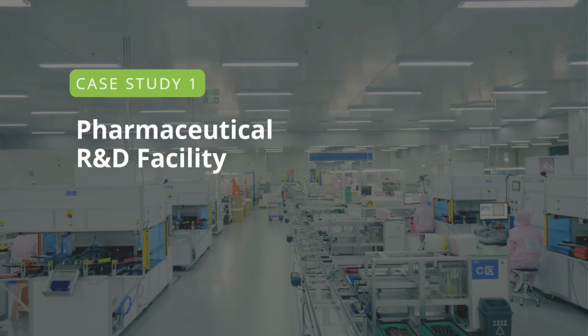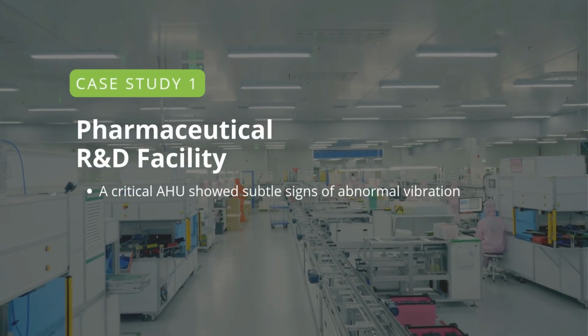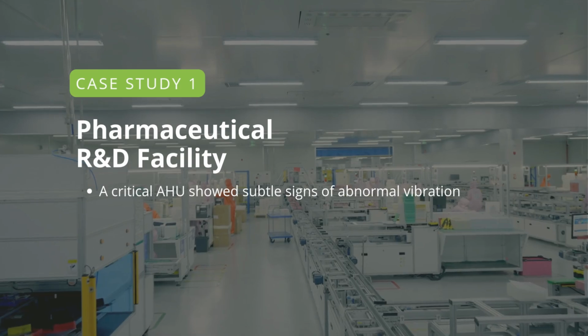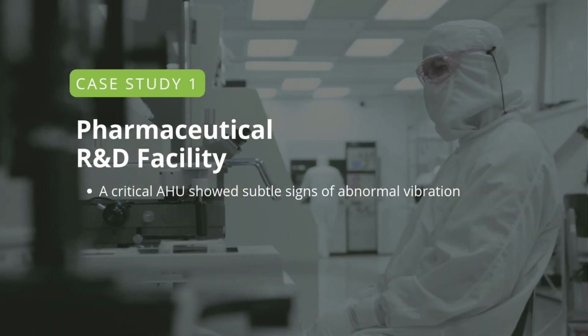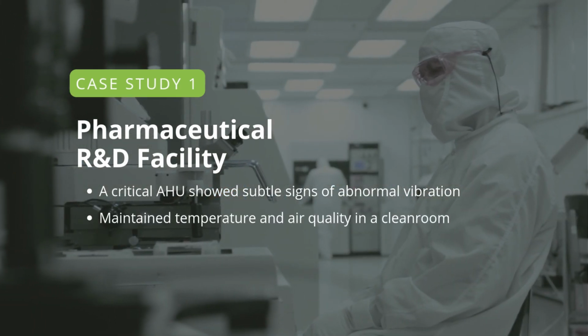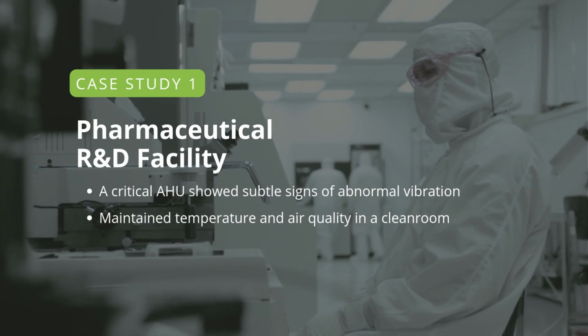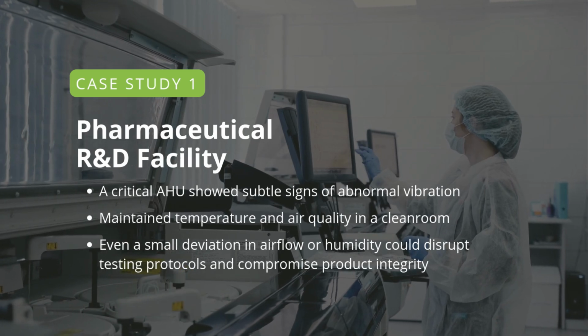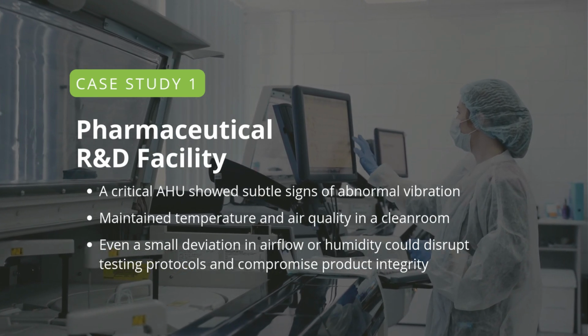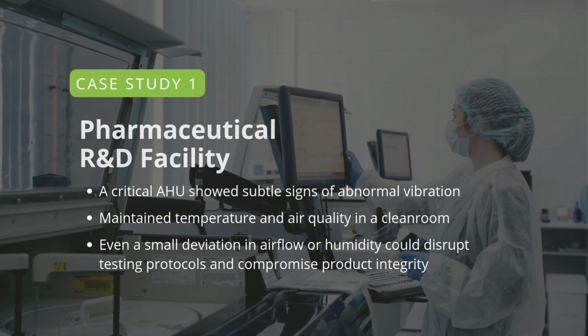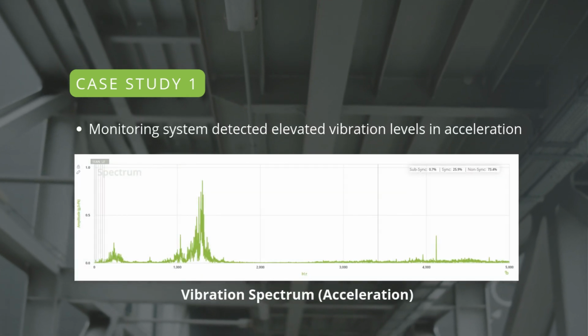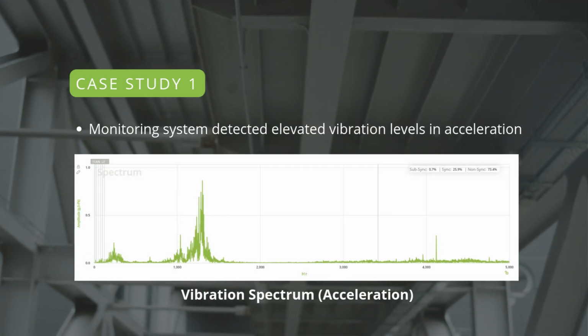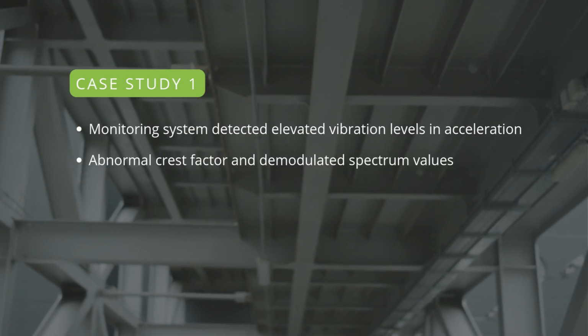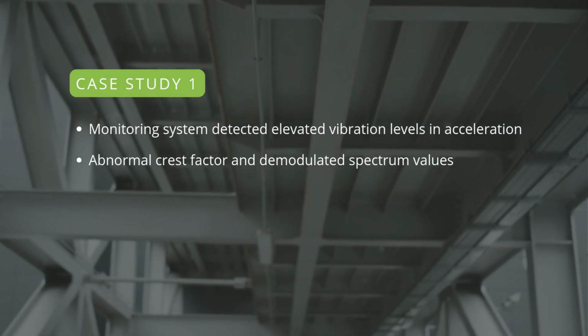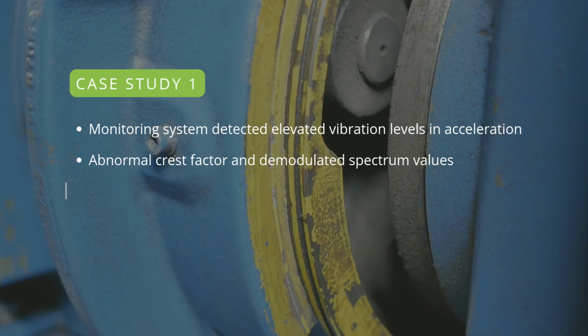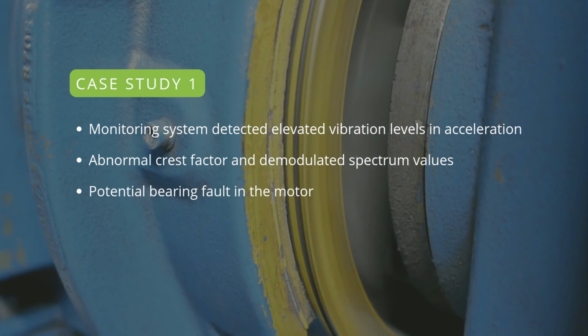At a pharmaceutical R&D facility, a critical air handling unit began showing subtle signs of abnormal vibration. The unit was responsible for maintaining temperature and air quality in a cleanroom, an environment where even a small deviation in airflow or humidity could disrupt testing protocols and compromise product integrity. The monitoring system initially alerted the team about elevated vibration levels in acceleration, along with abnormal crest factor and demodulated spectrum values, all pointing towards a potential bearing fault in the motor.